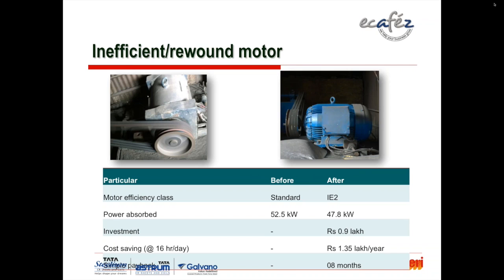Of course, IE3 also could be there, but as you know, there are different classes now. IE2 is the more energy efficient motor. It has a design energy efficiency of 93.5% compared to 91.7% for a standard motor of similar size. So the power which was required to operate this, as measured, was 47.8 kilowatts.